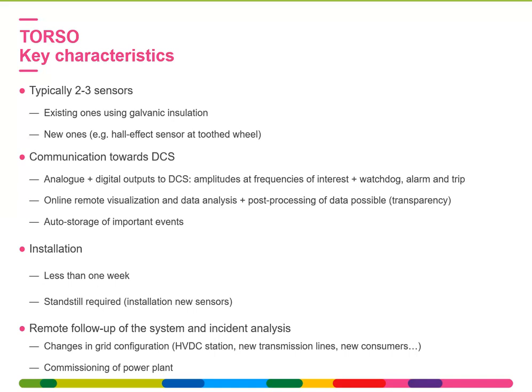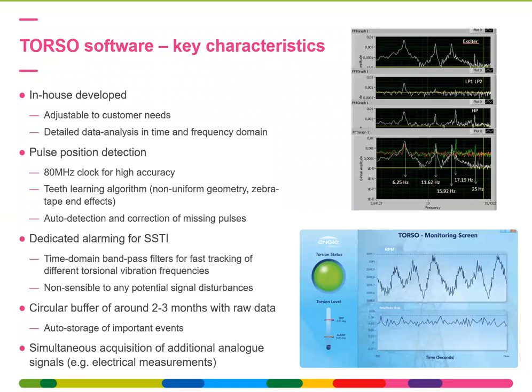Installation of a system is typically less than 1 week. If sensors have to be installed, you need a standstill to be able to install them. And remote follow-up of the system is possible. For instance, if you have any changes in grid configuration, like a new HVDC system, we can closely follow up whether this excites the system in torsional vibrations, yes or no. Also, when commissioning the power plant, sometimes it's useful to follow up remotely to check whether everything is working as it should.